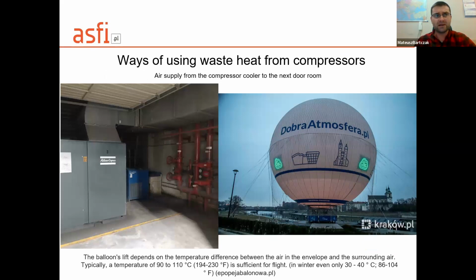So, two kinds of ways of using heat from a compressor. I show this slide because sometimes I hear from my clients, we recover the heat from compressors, we have summer and winter dampers, and in the winter we direct this air after the cooler to the production plant through the wall of the compressor room. At this point, I always mention a useful fact. Curiously, balloons fly at a temperature difference of about 60 degrees.